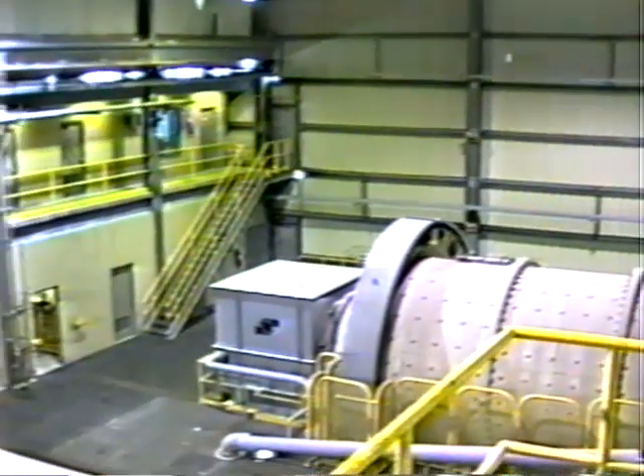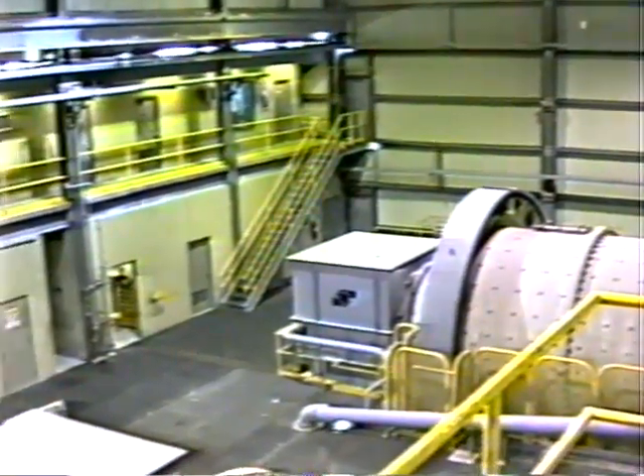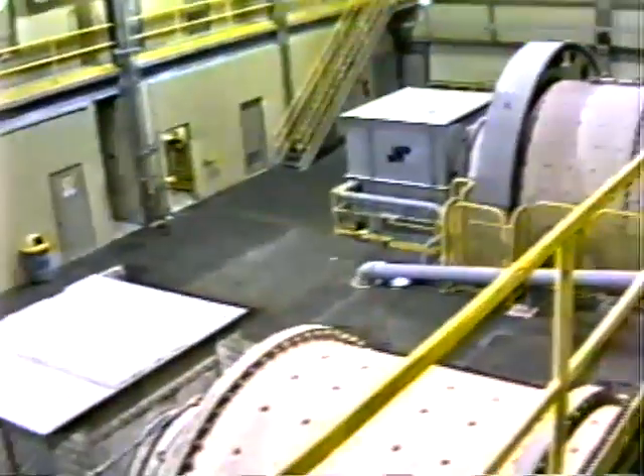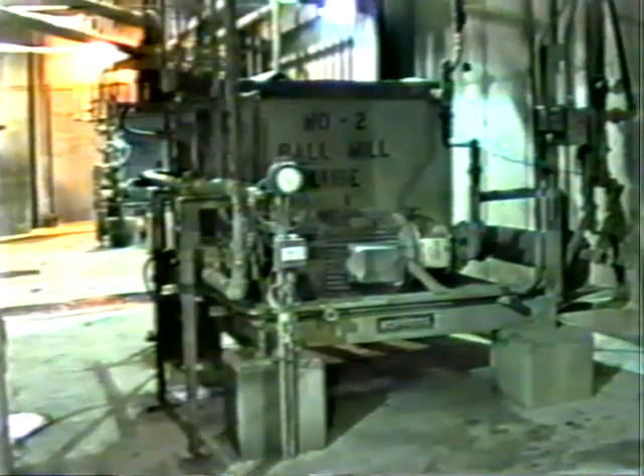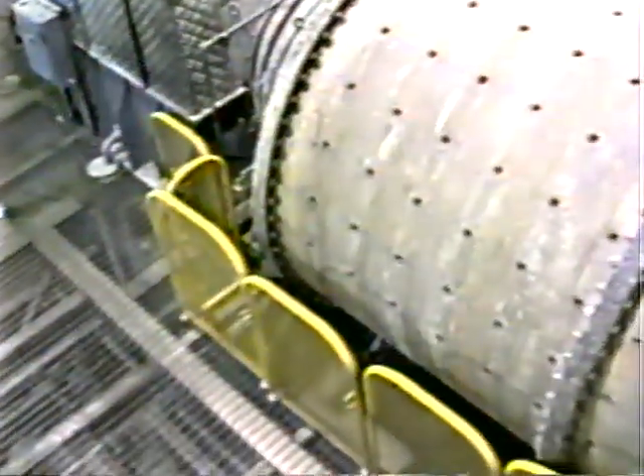Prior to mothballing, we added a rust inhibitor to the circulating systems on these mills to coat the inside of the bearings, journals, and pipelines on it. The mills were jacked up and installed on cradles, so there's no pressure on the main bearings of these mills here.